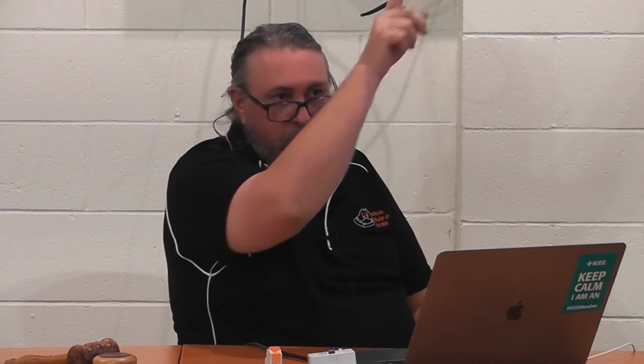But I think DC is arguably a little more dangerous than AC. The reason for that is that all these AC rated devices rely on the zero crossing of the voltage. So AC, obviously, sine wave, don't tell you that. If there's a fault, the fault will keep going as the voltage rises and comes down, but as it gets to the zero point, there's no volts, then there's no potential, and the arc will clear. But if you've got 300 volts from, say, a solar PV system, it won't stop.